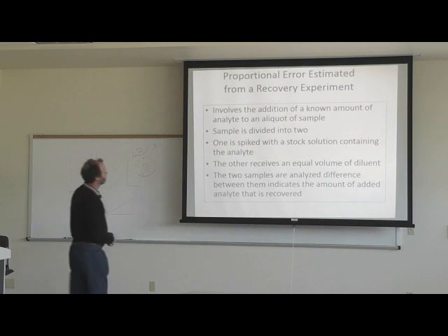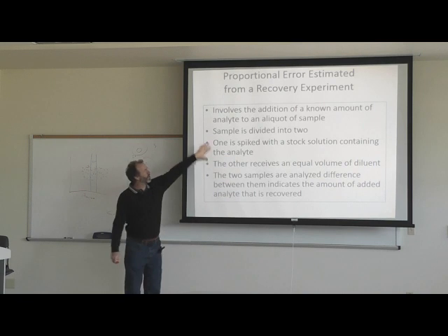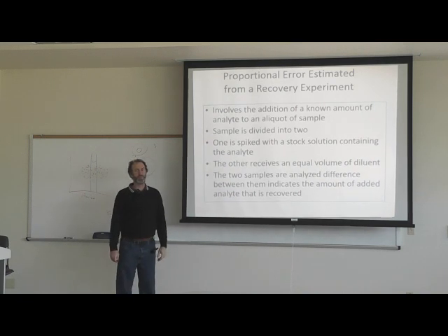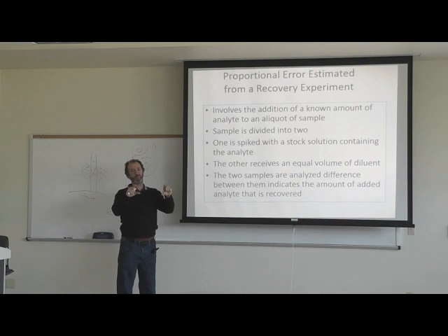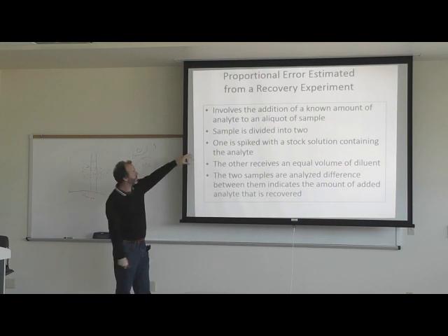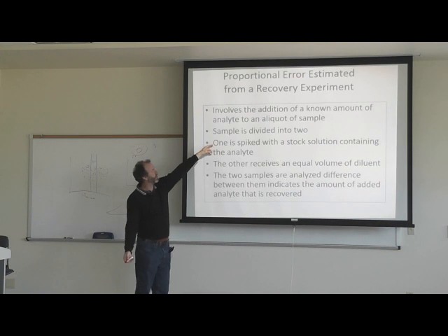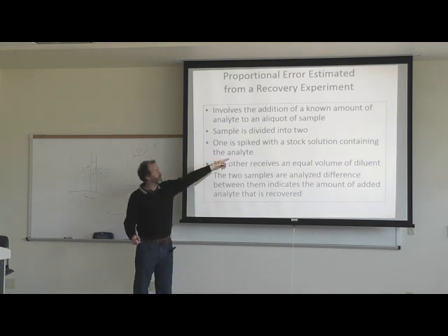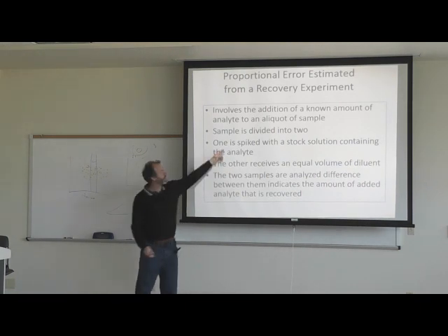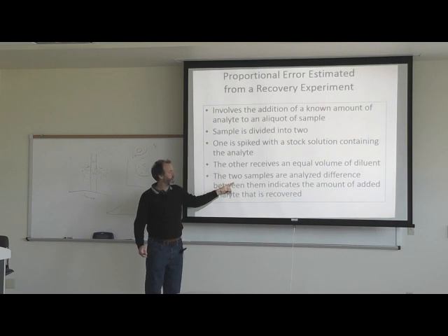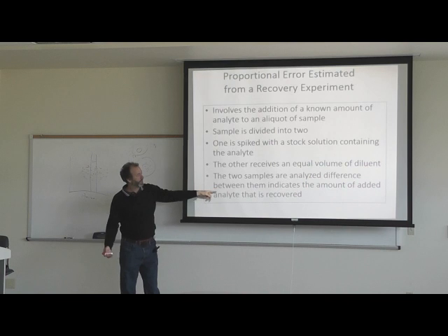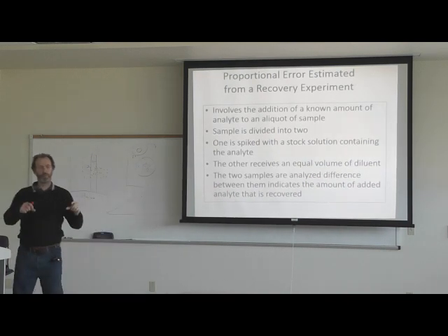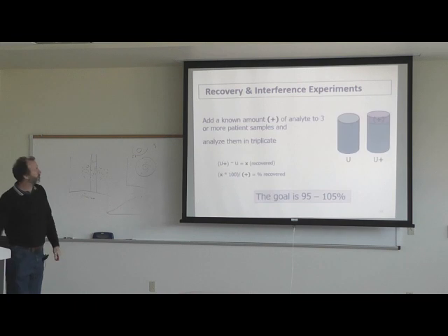Proportional errors estimated from a recovery experiment: you have two aliquots of the same sample — one is spiked with a known amount of analyte, the other receives equal volume of diluent. Both are analyzed. The difference indicates the amount of added analyte recovered. You add a known amount to three or more patient samples, analyze in triplicate. Percent recovery equals the recovered amount times 100 divided by the amount added, and the goal is between 95 and 105%.